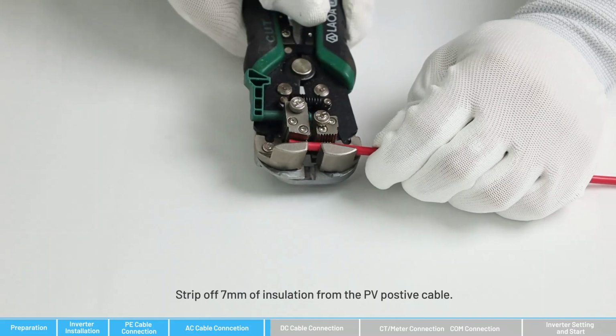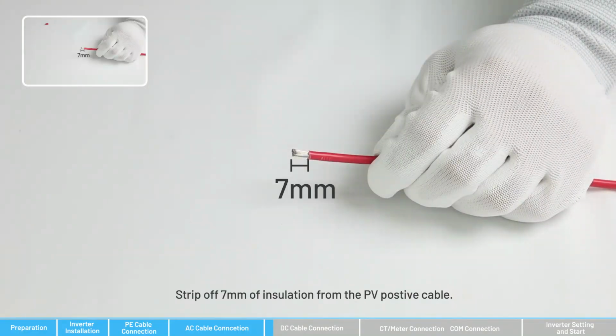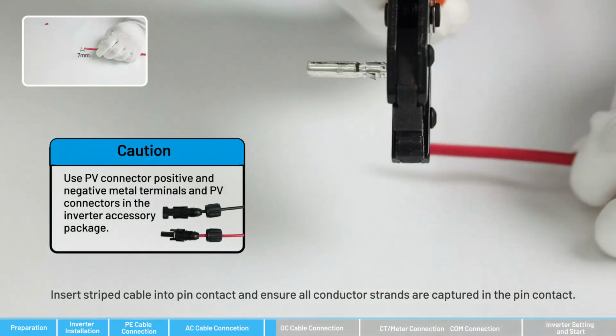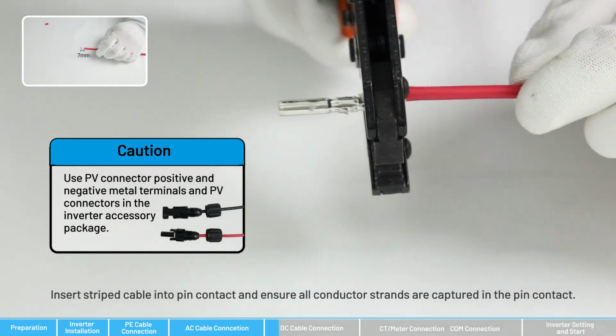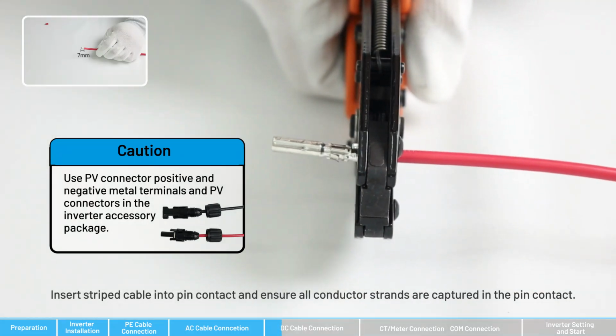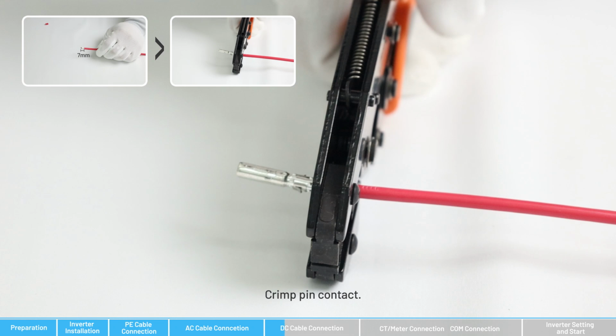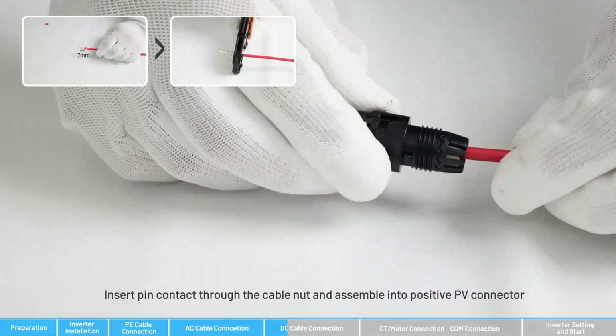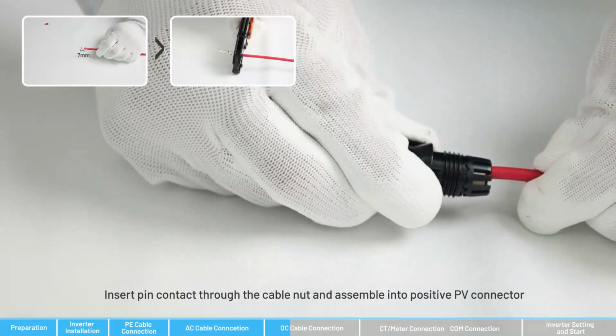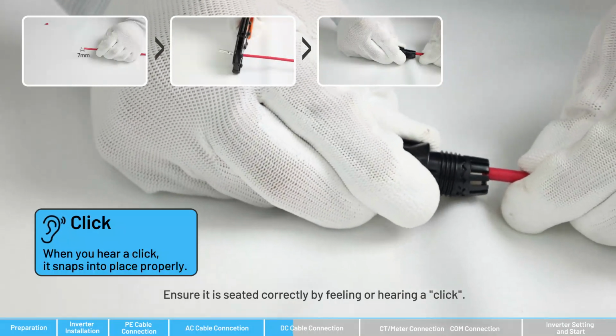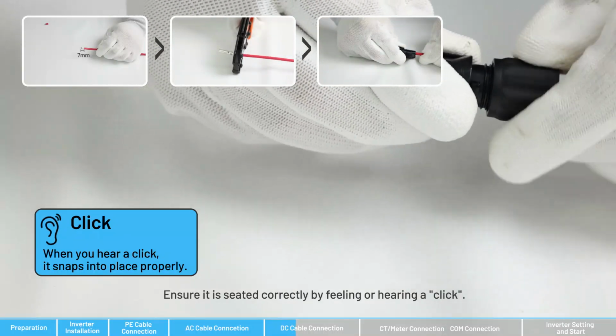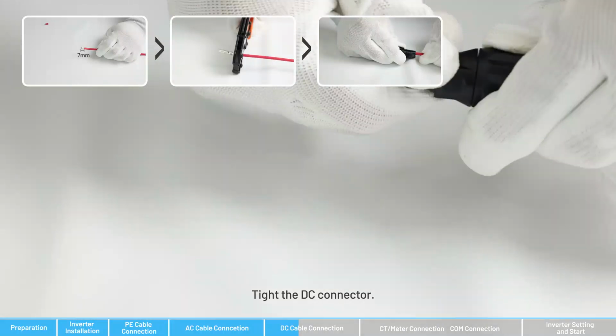Strip off 7 mm of insulation from the PV positive cable. Insert the stripped cable into the pin contact and ensure all conductor strands are captured in the pin contact. Crimp the pin contact. Insert the pin contact through the cable nut and assemble into the positive PV connector. Ensure it is seated correctly by feeling or hearing a click. Tighten the DC connector.